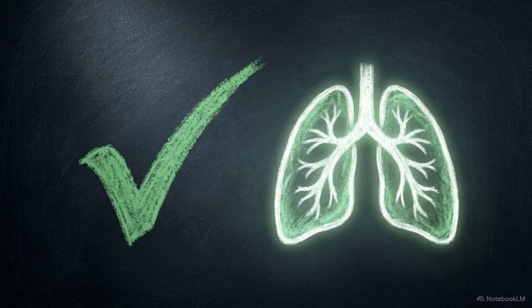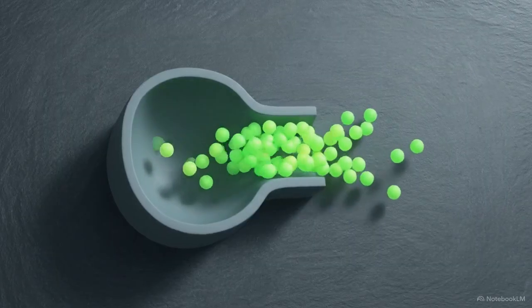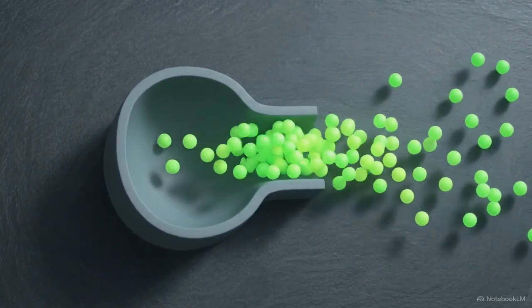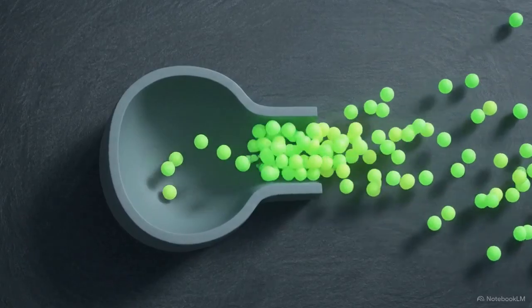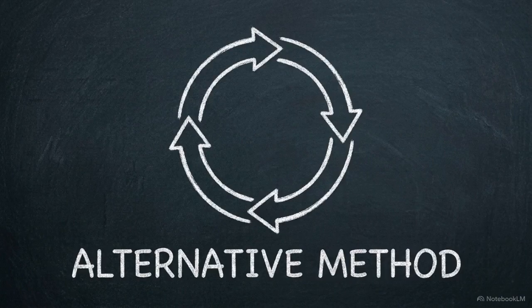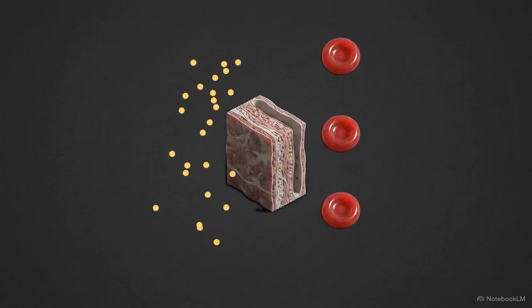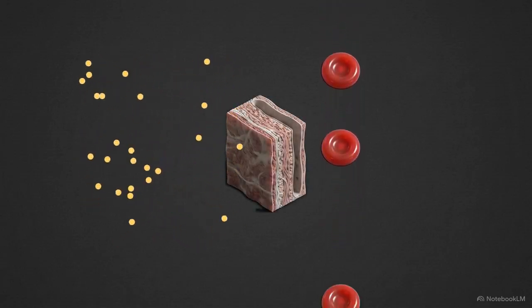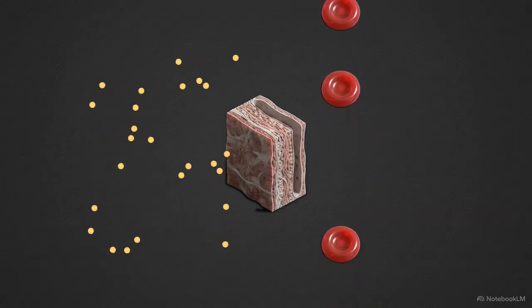The nitrogen washout test successfully calculates FRC, but it relies entirely on the premise that the gas can physically exit the alveoli to be collected and counted. The helium dilution test uses a closed-circuit alternative to the washout method. Helium is chosen because it is highly insoluble in blood. It will not diffuse across the respiratory membrane and ruin the conservation of mass equation.